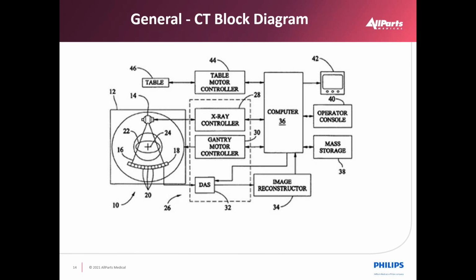Okay, so we have a gantry controller that rotates the gantry at a given speed very accurately, and also triggers, working with the computer in this case, the DAS to acquire data. As we rotate the gantry, we get triggers to sample our collective view of data from each angle, and then the DAS is collecting and converting that data and forwarding it to the image reconstruction process. In this case, it would be our scan data disks, our raw data disks, that we would call the disk drive array, that would get the raw data, and then we would process that into a final image. That final image would then go to the computer and be saved in today's market as a DICOM image, so the operator could view that image. So we would have mass storage that would typically now be a DICOM server somewhere in the hospital network. But with original scanners, that was actually extra hard drive space or other hard drives that would save that image data, so you could view that as well, known as process data.